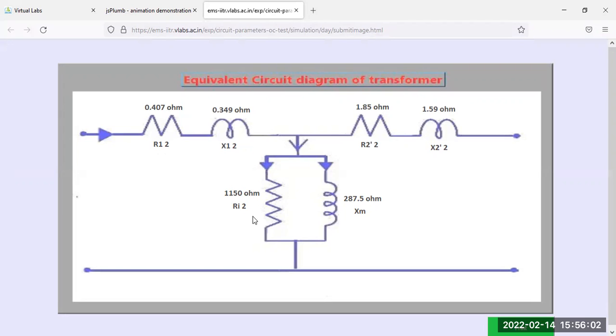So RC equal to 230 divided by no load current into cos phi 0. The no load current is 0.9 into 0.24. From this you will get the value of almost 1150 ohm.